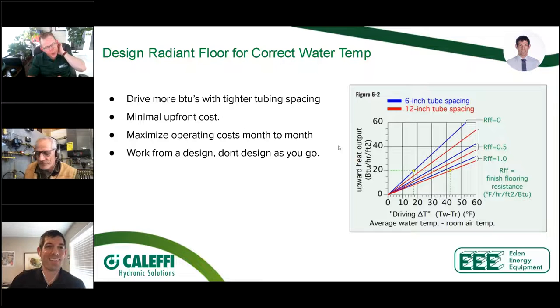One of the comments we just got, it's a good comment. So Jason from Building Knowledge, thank you for the comment, has pointed out that going from 12 inch to 6 inch spacing does add some challenges, and he's specifically looking at head loss. So when we go from 12 inch to 6 inch spacing, we actually have to redesign those circuits. It's not a matter of just going where I had 12 inch, I'm going to do 6 inch. CSA B214 helps on this. If we actually follow code, we'll realize that if it's half inch tubing, we can't exceed 300 feet per circuit.